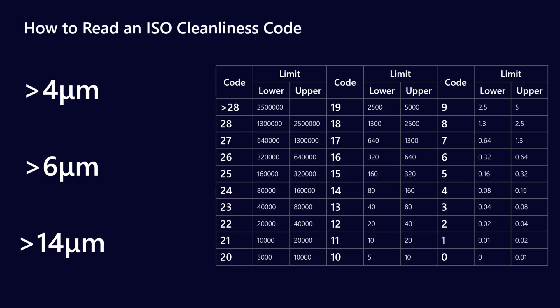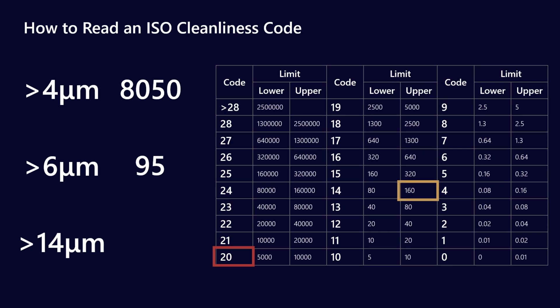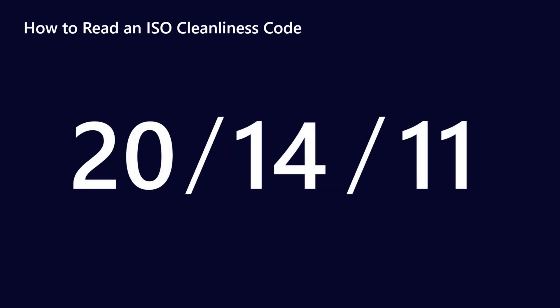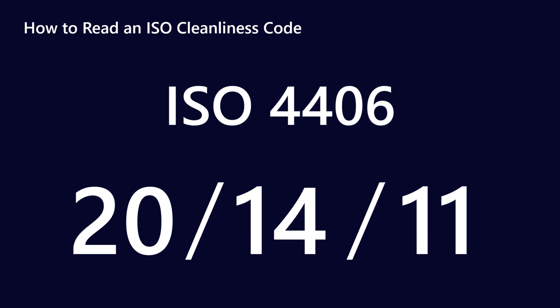In a previous video we talked about how to read an ISO cleanliness code. As an example, with 8050 particles above 4 micron, I go down to the table — 8050 is between 5000 and 10000, giving a first number of 20. Likewise, 95 is between 80 and 160, so the second number is 14. And for 14 microns, that's between 10 and 20, so the third number is 11, giving my three-number ISO cleanliness code. That video described ISO 4406, which is not a test method — it's actually a classification system for cleanliness.